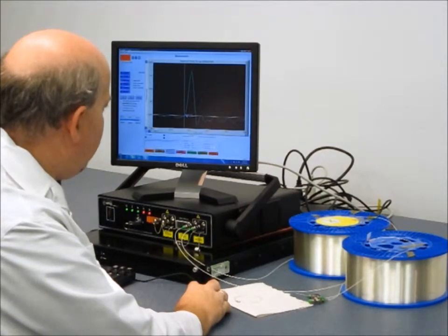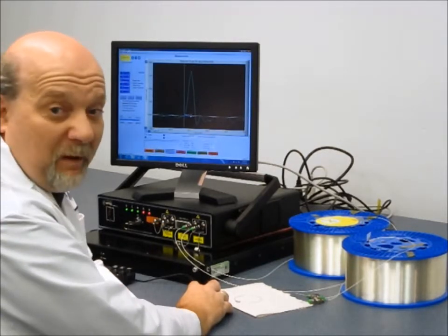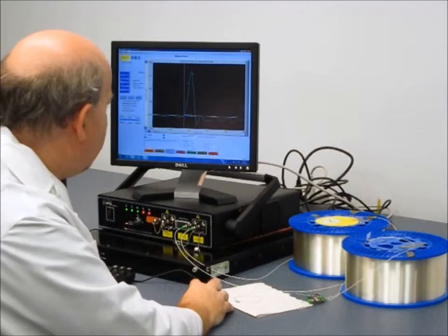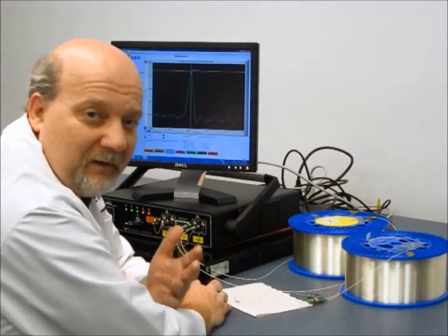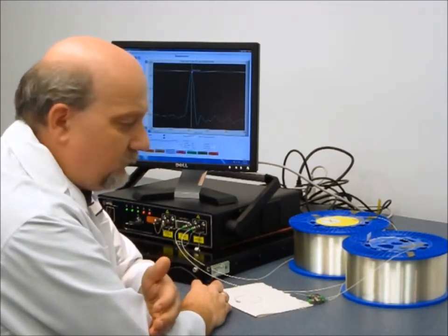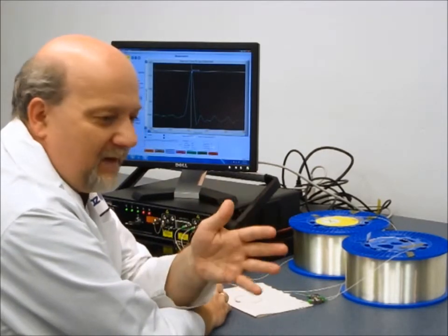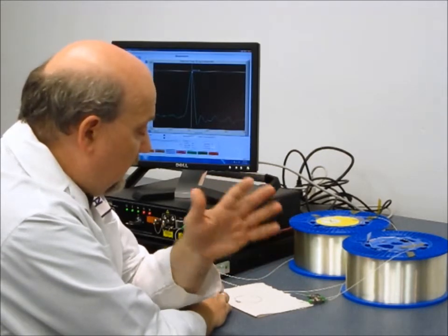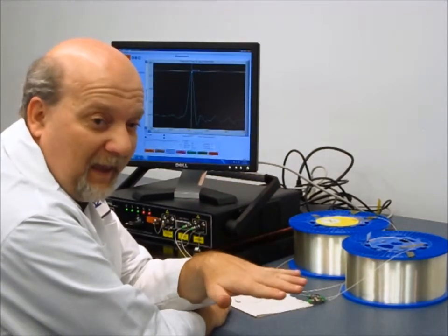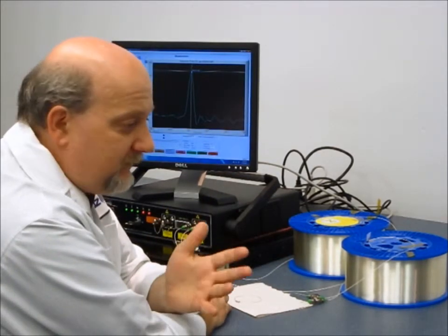And if we look here at 25 kilometers and 38 meters, we're at our baseline temperature, basically a variation of only about 0.3 degrees. 3 meters up, this is where my hand was, and we see a 5-degree increase in the temperature. As I mentioned earlier, room temperature here is about 25 degrees. My hand temperature is a few degrees below my core body temperature, so it's about 33 degrees. That's a temperature difference of 8 degrees, and the fiber is seeing the average between my hand on the top and the table beneath. So a 5-degree reading in the temperature is quite reasonable.